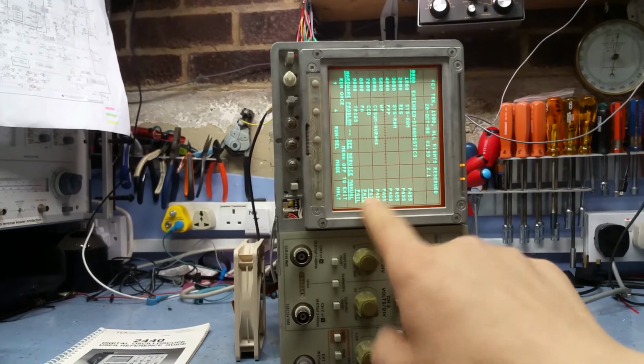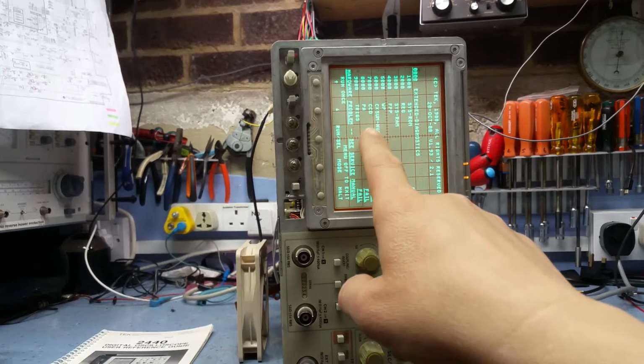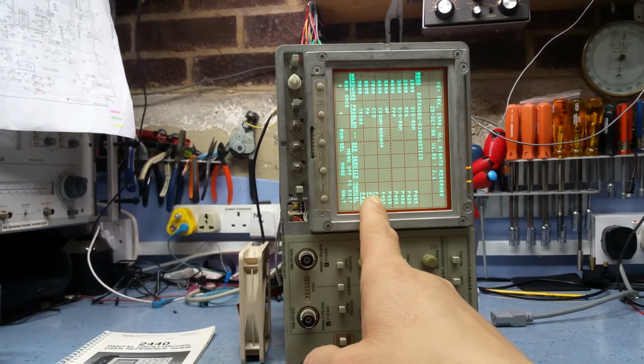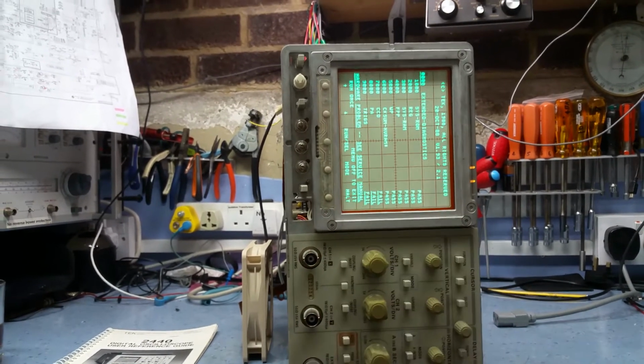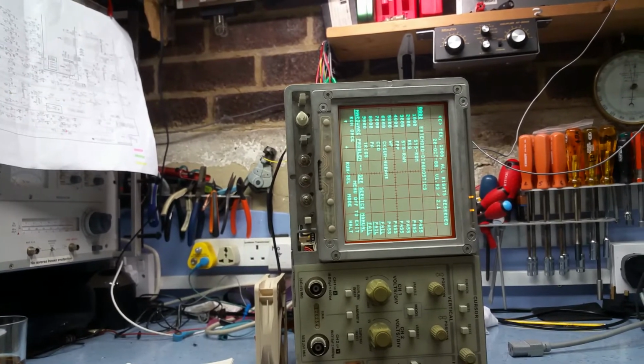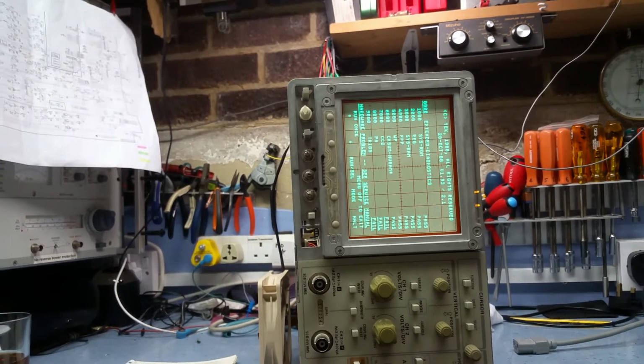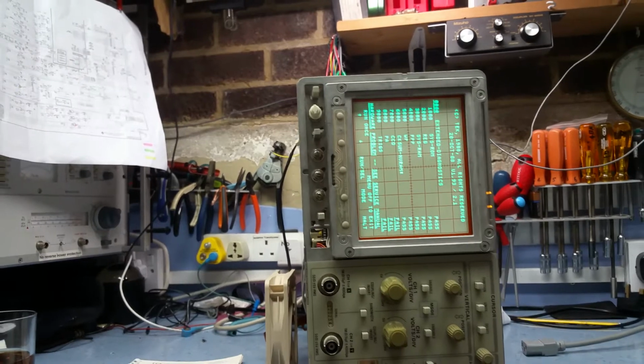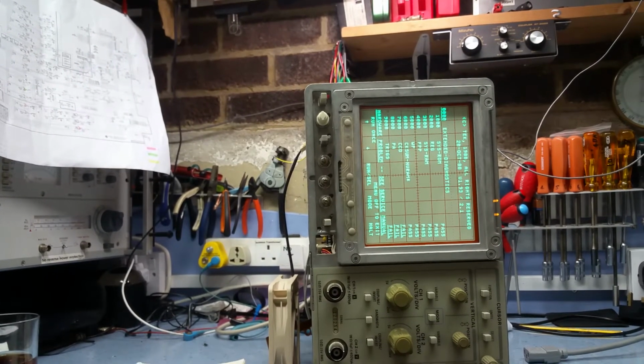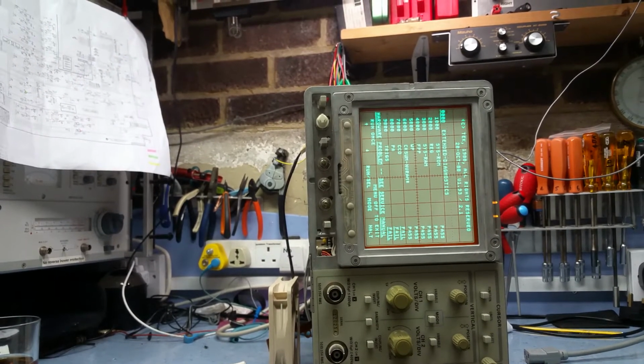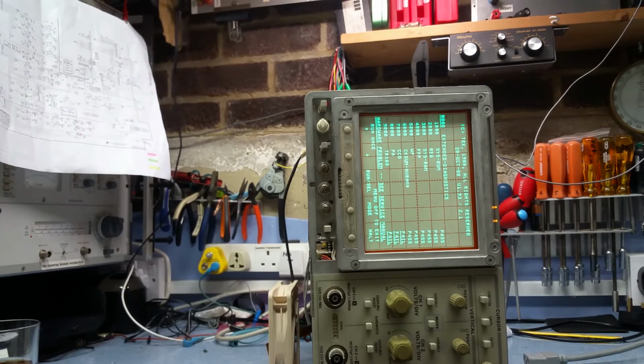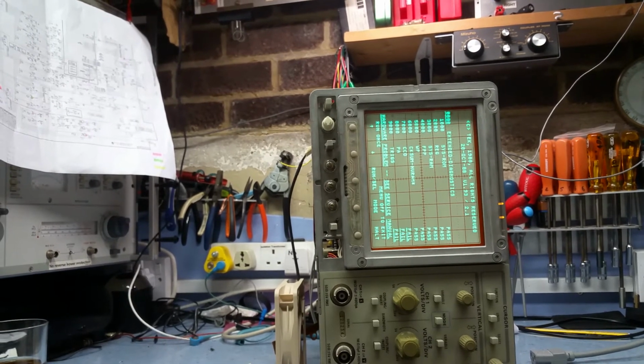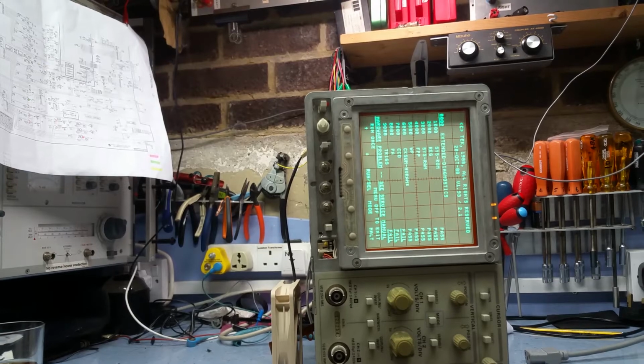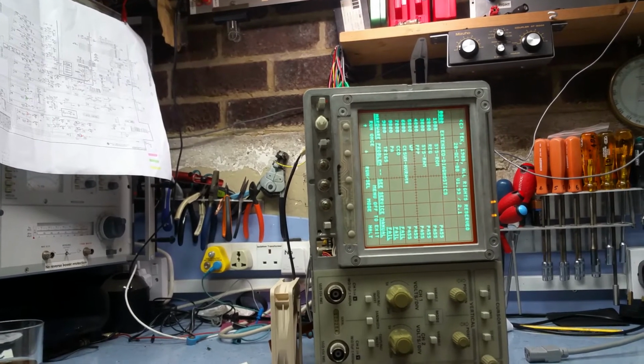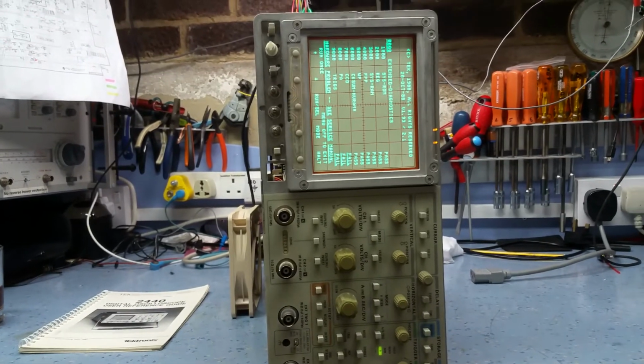But I think the reason why these have failed here is if you look, the checksum's got a problem with it, and it can't continue any further because it probably stores data in non-volatile RAM for calibration, things like that, and it's not doing that, so everything's out of whack. So I think basically the CCDs, the preamplifiers and the trigger, there's no problem at all with them. It's just I can't store calibration in the non-volatile RAM. So that's where we are with that at the moment.